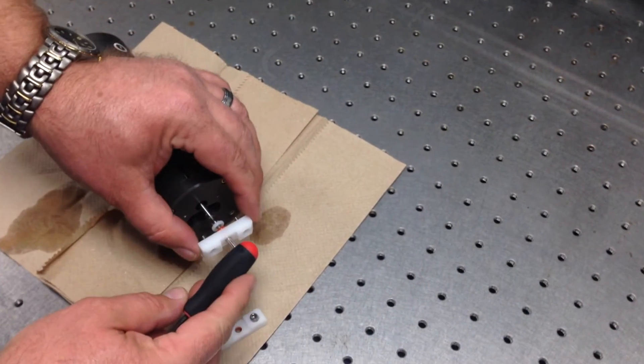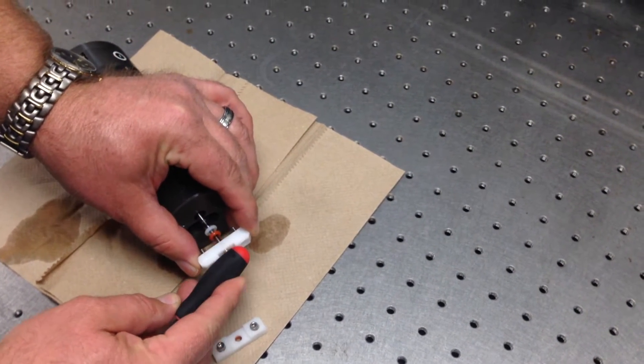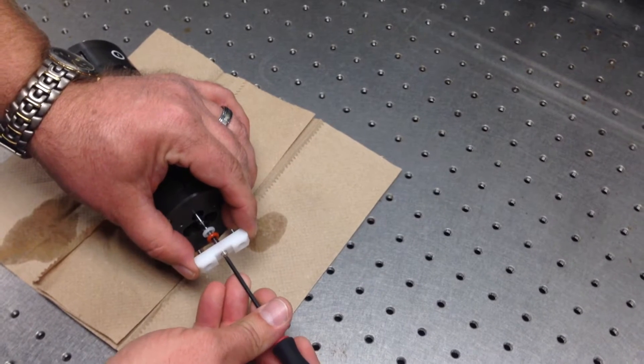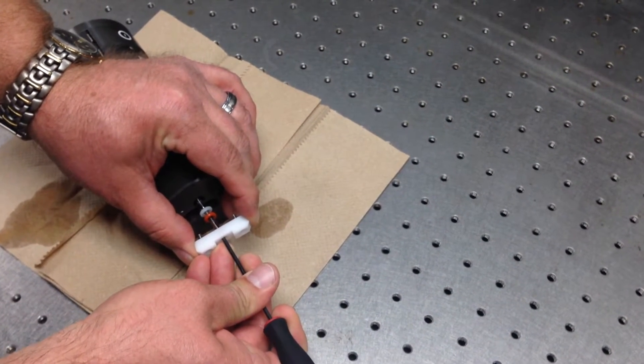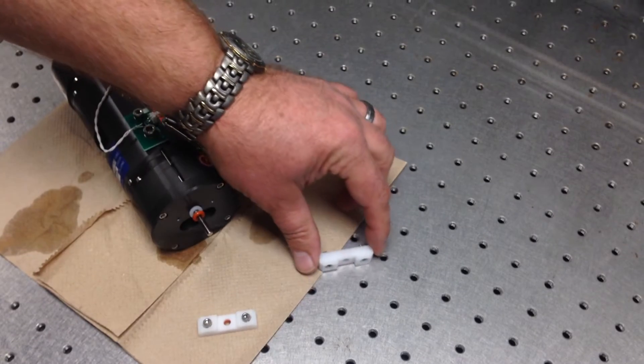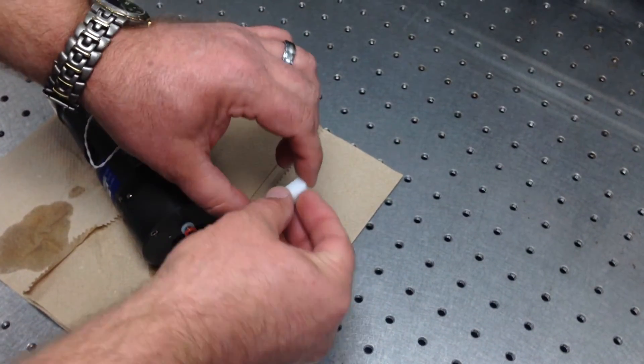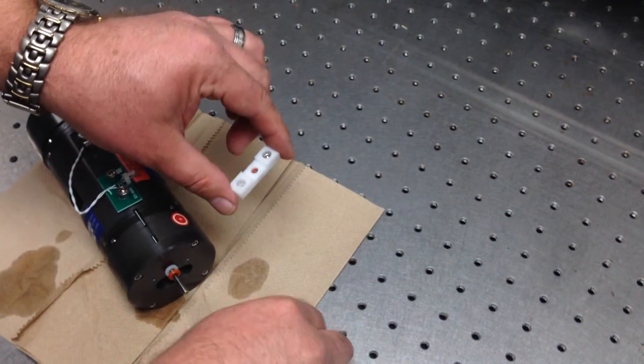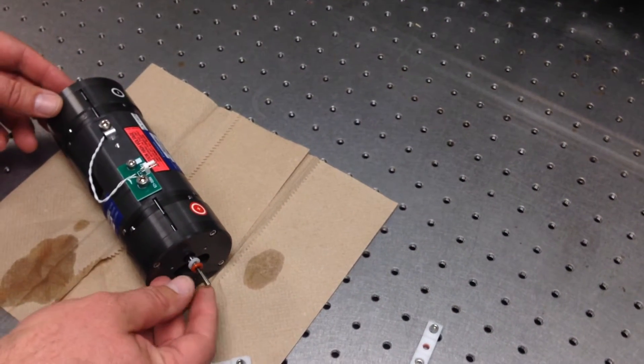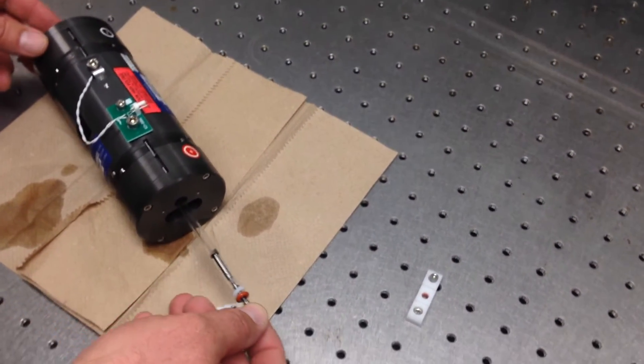Now notice right now that the lamp is wanting to come out without any effort, it's really loose. The old one needs to push. That's right, and that's typical. But this one has no liquid. So what you want to do is just slide the lamp out.